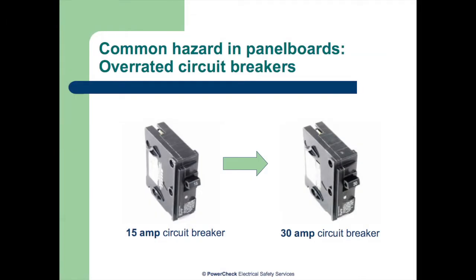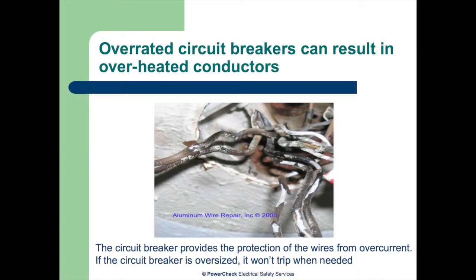The common hazard we see in most of the older panels that didn't have enough space is overloaded circuit breakers. Circuit breakers were designed for 15 amp branch circuits for running your lights and your receptacles. If you start running a basement suite off existing breakers, the breakers are going to trip. So people who don't really know what they're doing will fix it by changing the breaker for a 30 amp. Well, what they've effectively done is take away the circuit breaker protection that your circuit needed. And that's what happens: the result of oversized circuit breakers combined with excessive electrical demand.